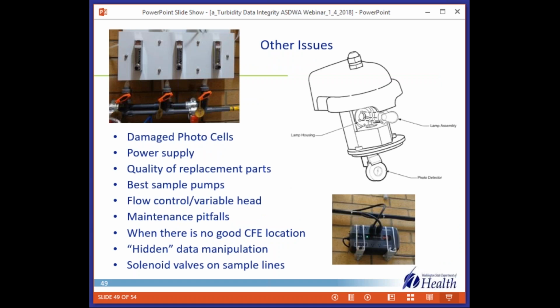So other issues, this could have actually been 10 slides, because the more you dig into the issues around turbidity, the more things that you find that are important. So this is a kind of laundry list. I want to highlight a few. In Alabama, the drinking water program there alerted us to the fact that some of the photocells out there were damaged. They were losing the protective oil that was in the photo detector, and so when you turn those on their side, you don't see the normal bubble and that can mean that the photocell will be less reliable going on. So they contacted the manufacturer and learned that those should be replaced if you find that the bubble is not present.